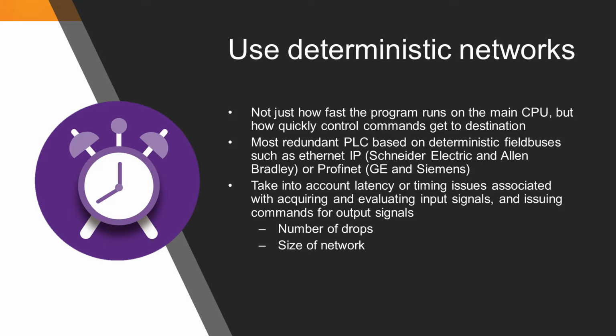But within control systems, we can't develop high availability systems based on randomness. We need consistency, and we need to understand, when we issue a command from one controller, it's not only the command coming out of the controller - it travels over the network, is recognized in the distributed I/O module, and then an action is taken to control a motor or output, or vice versa, where you're reading a temperature and then making a decision. So there's network latency and reaction times of all the components within that data acquisition or command stream.